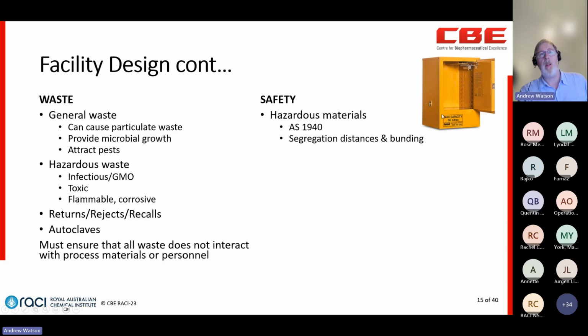You can have no electrical equipment, power outlets, door swipe outlets, or anything with the potential to generate a spark, within this zone, and it extends about 1.8 metres off the bottom of the storage or spillage space. This can be extremely constricting, particularly in small facilities where you've just got to have a little bit of isopropyl alcohol for sanitation and those sorts of things. It's something that's regularly overlooked.